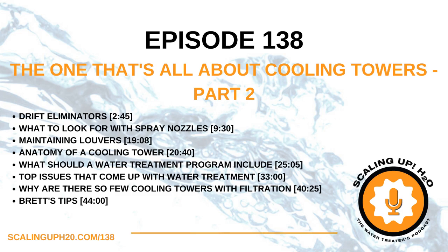With the zero bleed thing, I think the way to go against that is use the manufacturer's recommended water chemistry parameters. And I'm pretty certain if they're cycling up that high, they're going to be above a few of those properties. Probably calcium hardness for sure, alkalinity, and maybe even chlorides. So, that kind of takes them out of warranty.